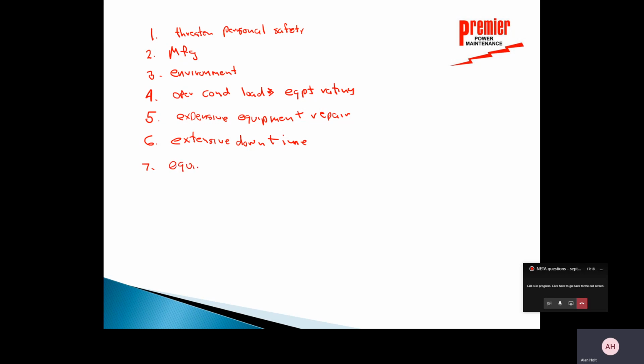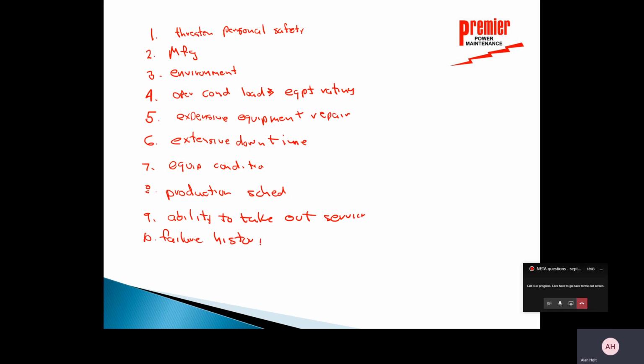Then you need to take into account the equipment condition itself. Number 8, production schedule. I mean, you can't shut everything down just for the whim of it. So you really do need to consider the production schedule, but that's way down pretty close. Then, how about taking it out of service? The ability to take it out of service. Again, that's pretty low, but it needs to be considered. 10 is failure history. What kind of history do we have on this particular piece of equipment or sister pieces of equipment? Those are both taken into account. And finally, inspection history. Maybe the infrared or oil history or something like that. So those would be the 11 items to be taken into consideration when you're developing a routine maintenance schedule per NFPA 70B.